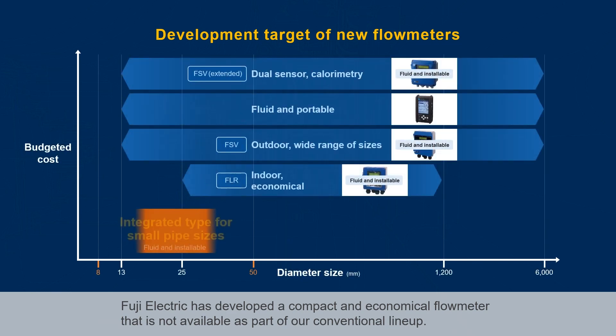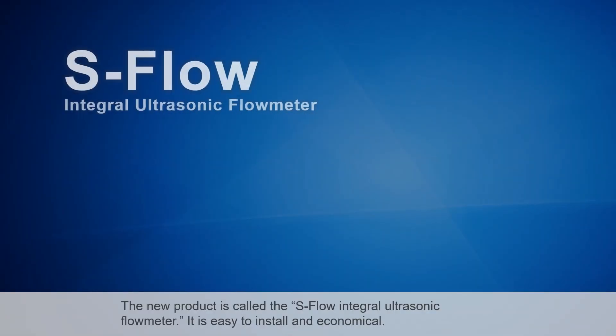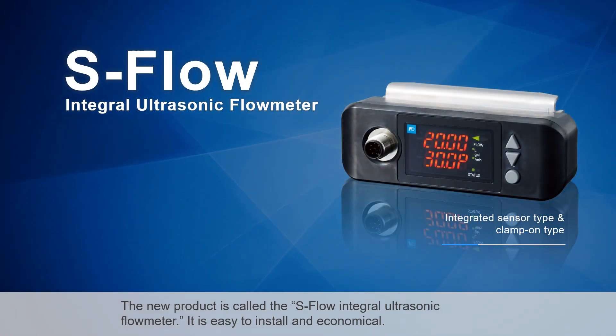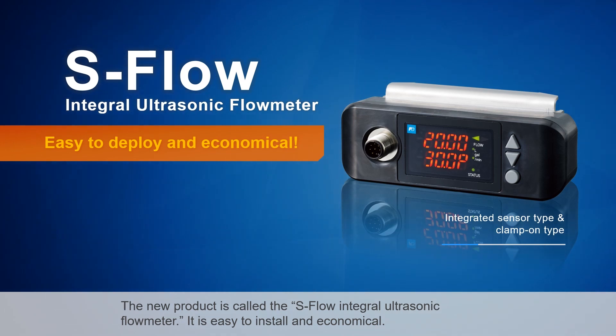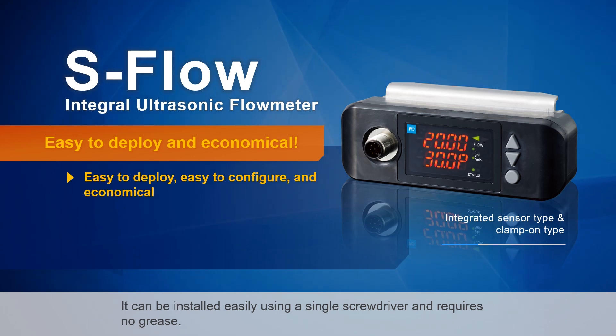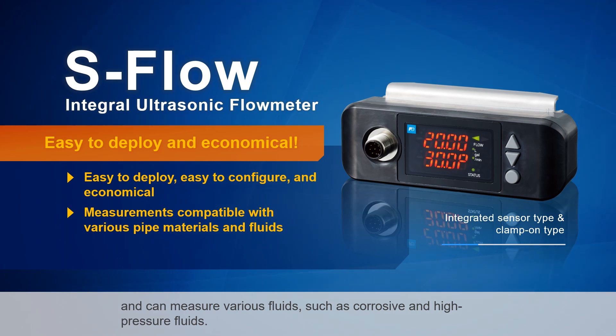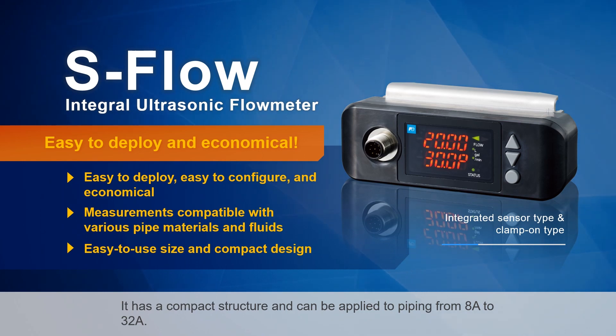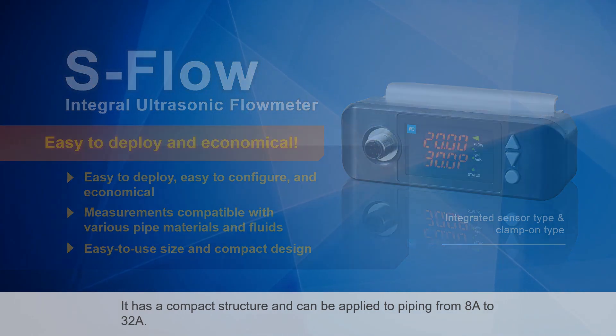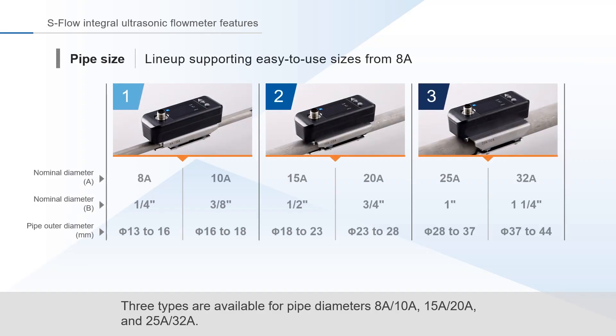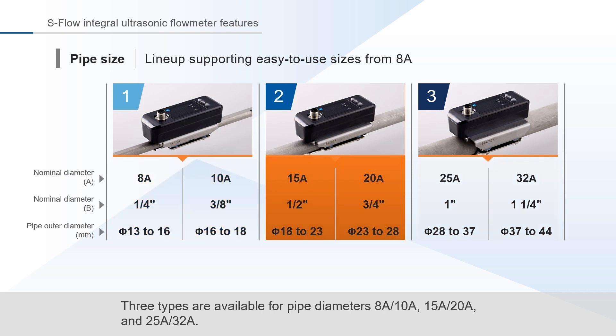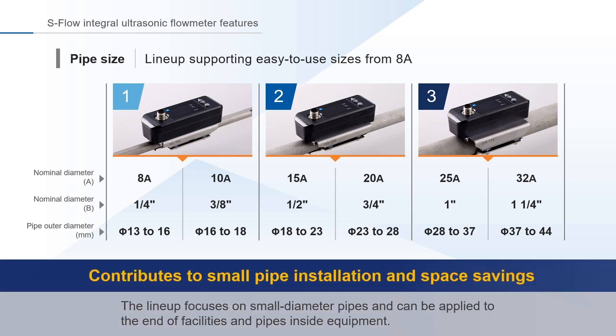Fuji Electric has developed a compact and economical flow meter not available in their conventional lineup. The new product is called the S-Flow Integral Ultrasonic Flow Meter. It is easy to install and economical — it can be installed easily using a single screwdriver and requires no grease. It can be used with a wide variety of pipe materials including copper and PVC pipes, and can measure various fluids such as corrosive and high-pressure fluids. It has a compact structure and can be applied to piping from 8A to 32A, with three types available for pipe diameters 8A–10A, 15A–20A, and 25A–32A. The lineup focuses on small diameter pipes and can be applied to the end of facilities and pipes inside equipment.